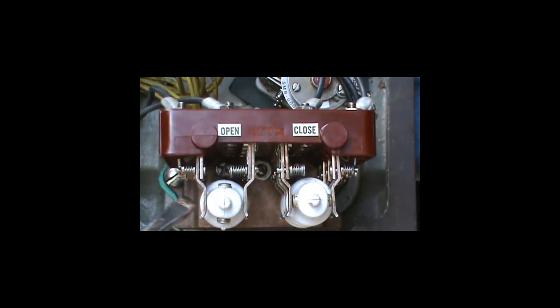Contacts are straight up and down. They're not touching the contact fingers. And there's no gap between the contact finger and the L-bracket or the contact finger and the barrel of the switch.